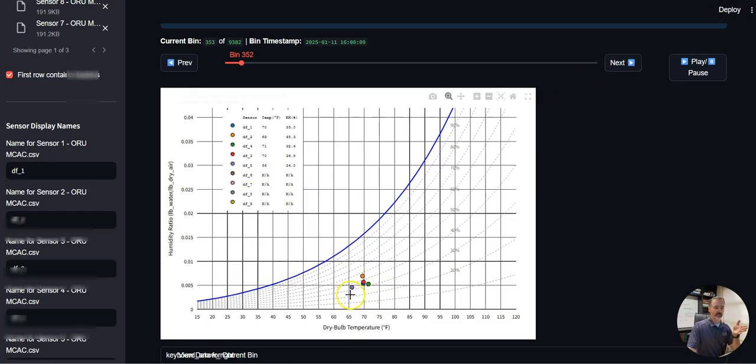This DF5 is actually outdoor air, and these are sensors above insulation but below a metal deck in a gymnasium. And so as outside air in time starts getting colder and colder, you can see one particular sensor starts tracking it, and so I can tell that there's not enough insulation. It actually passes it at this point, the sensor that's not the outside air, which is just like hysteresis, just measuring a little colder, but you can tell there's just no insulation there, so it's absolutely tracking outside air.